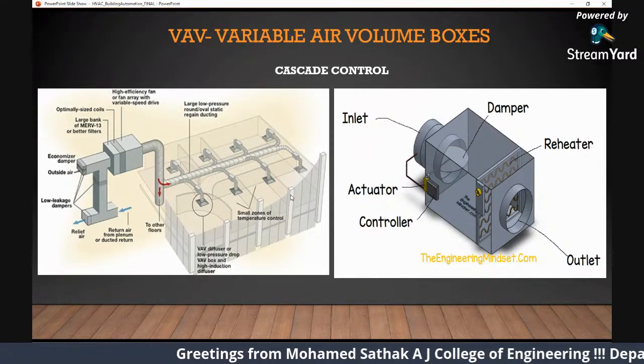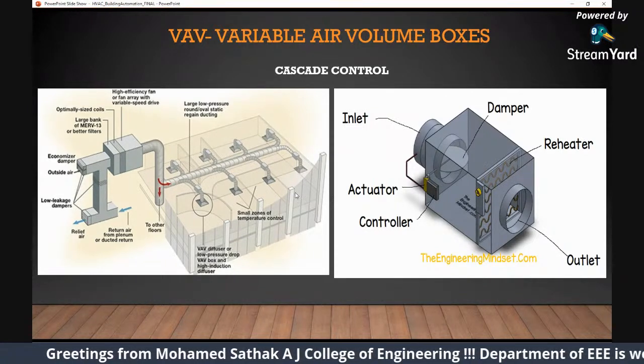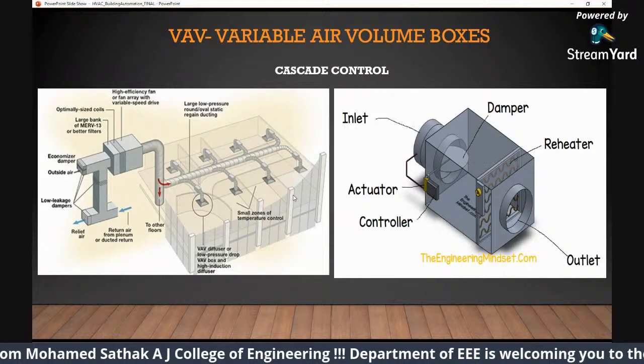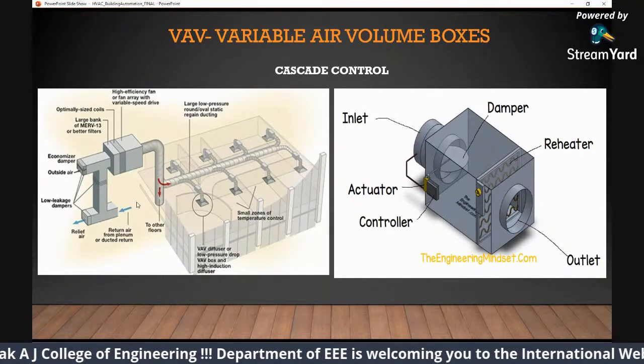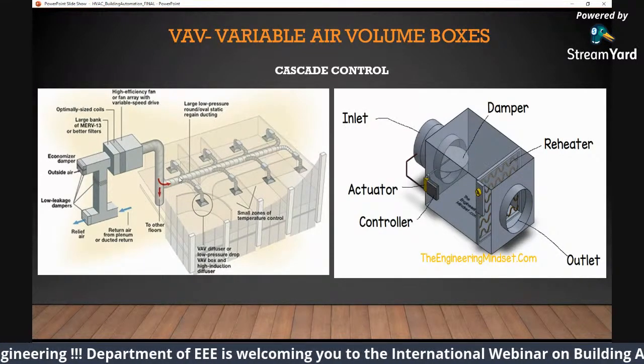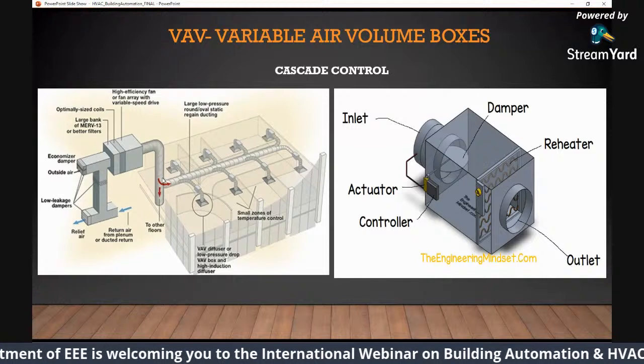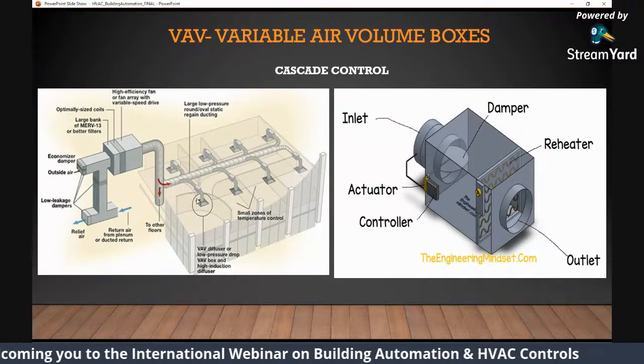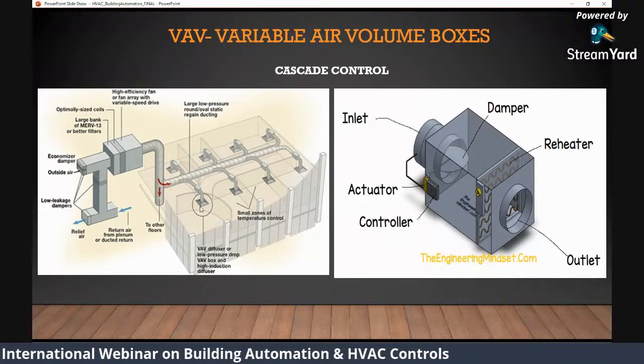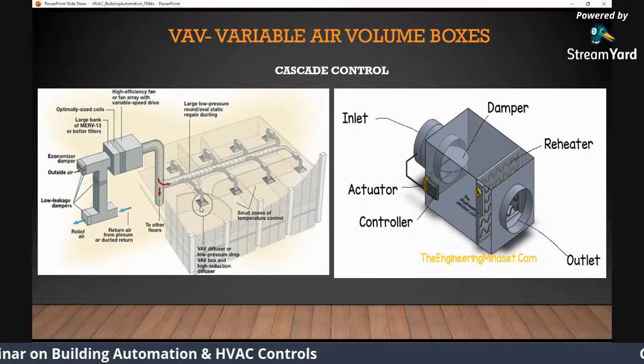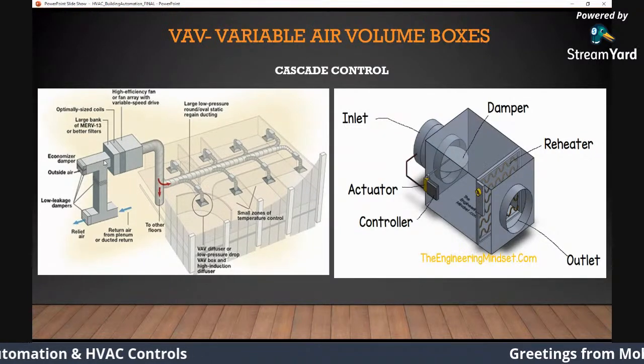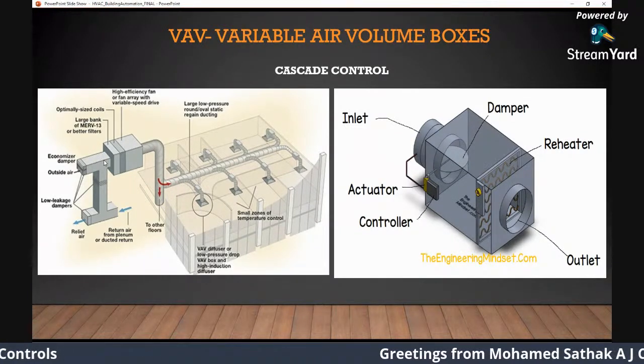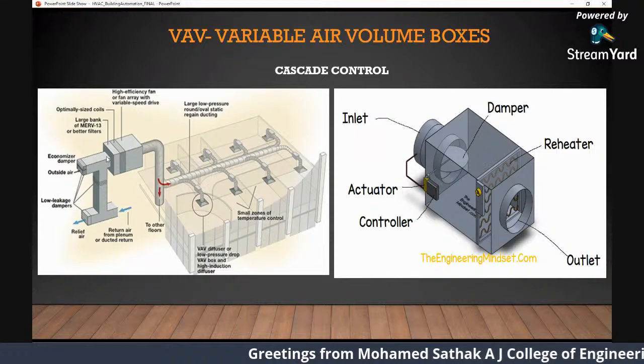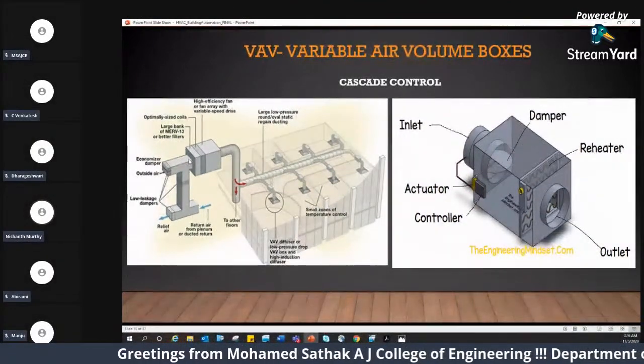Now this operates on the principle of cascade control. All it has is a damper and a temperature thermostat in it. So let's say, look at the picture on your left. Each room has a box in it. If you see the ductwork, the ductwork goes to each room individually. There's a circled part which says VAV diffuser box. That's a VAV box. Now this duct gets air from your AHU. Each room has a T stat. We call it a thermostat, a temperature control.